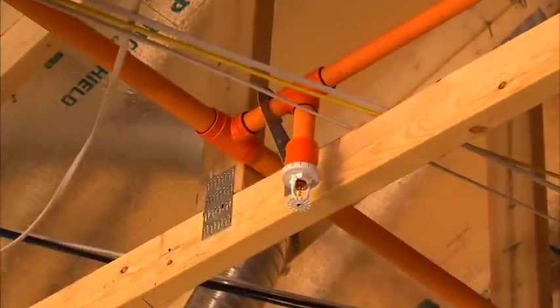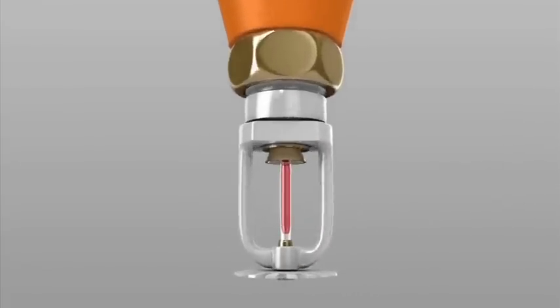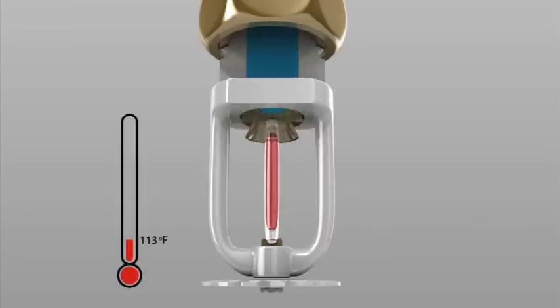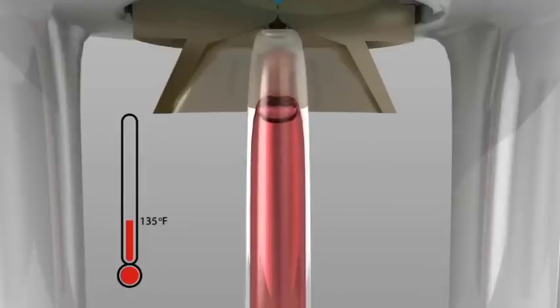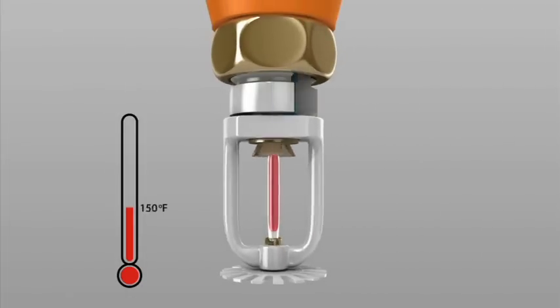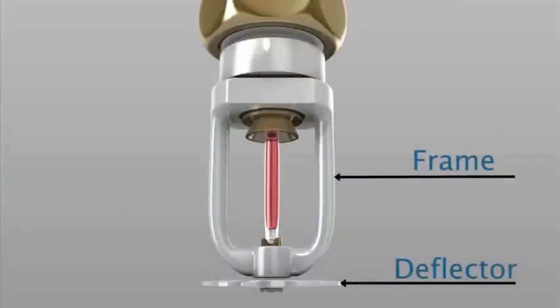It's important to understand how a fire sprinkler system works to understand water supply needs. Sprinklers are linked by a network of piping, typically hidden behind walls and ceilings. A sprinkler is very simple—basically a heat-sensitive plug on a piping system. The plug is most commonly held in place by a glass tube containing a liquid element that responds when the temperature near the sprinkler reaches 135 to 165 degrees Fahrenheit. At those temperatures, the liquid expands until the glass bulb bursts, releasing water, and a deflector properly distributes the water.